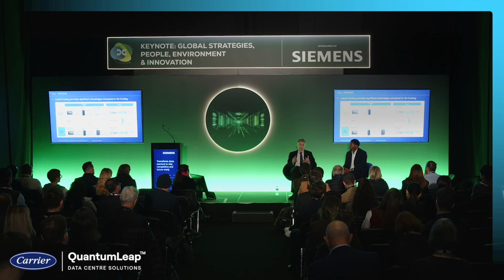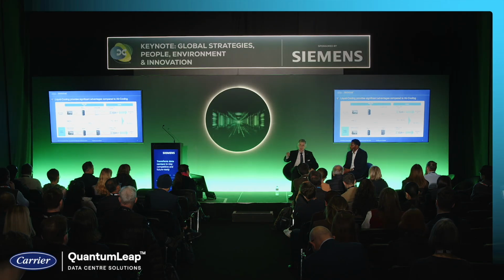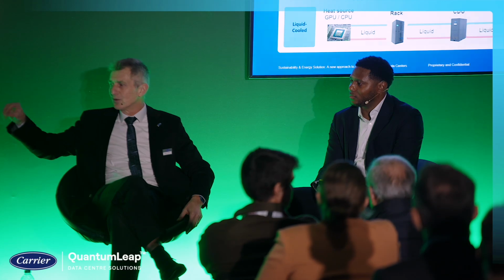So basically, as I said, you need not only to maintain the temperature of the chip, you need to move this heat outside of the data center, and eventually throw it away to the air, or maybe to district heating, or maybe to the sea. This picture, probably too busy, tries to show that this heat goes from GPU first maybe to a rack, and from rack to CRA, from CRA to chiller, and from chiller to outside, in the traditional air-cooled data center.